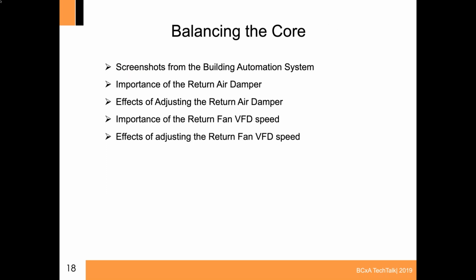This is also going to show the importance of the return air damper, its position, and the effects of it on the amount of heat recovery we get. We'll also show the importance of the return fan VFD speed and the effects of adjusting it. Prior to the final set of sequences, the return air damper was supposed to modulate to ensure enough air was across the core. However, in the final set, it got changed to being controlled on the building pressure, which kind of threw out the balance and one of the whole reasons for this tech talk.